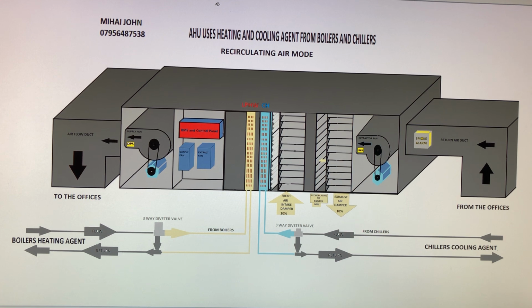When the damper opens, some of these switches close circuits which send an input to the BMS, telling the BMS that the dampers are healthy. So let's assume all dampers are healthy and we don't have any fault. The BMS tested the dampers, it's all good and perfect. Then the BMS will start the fans. So the fans are starting.